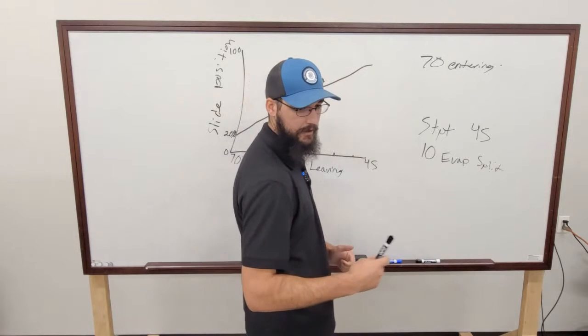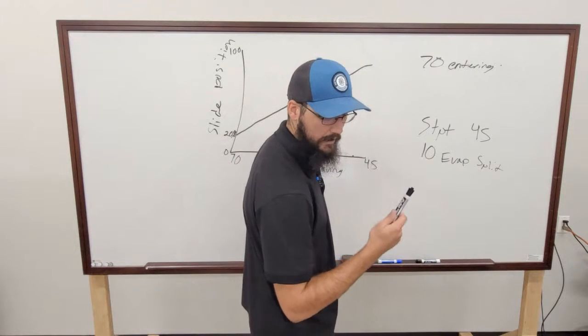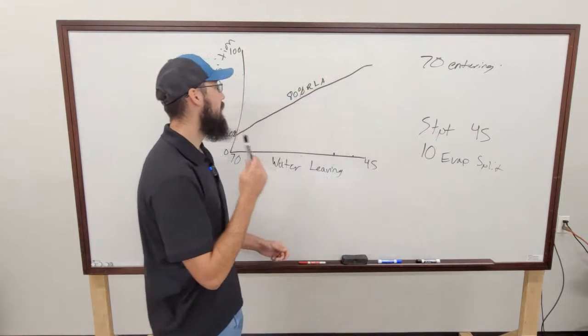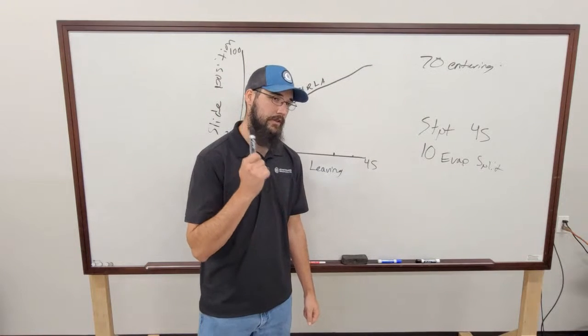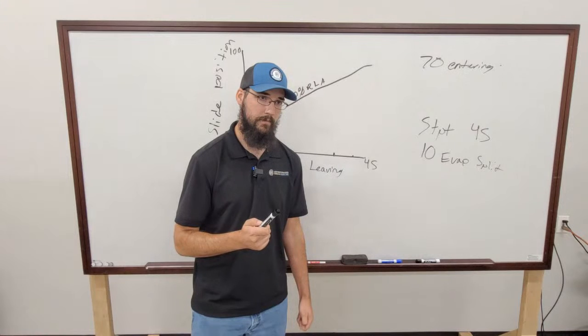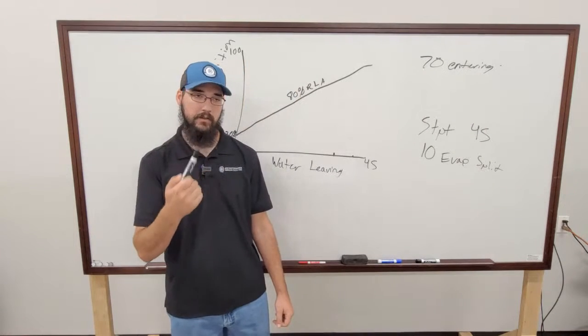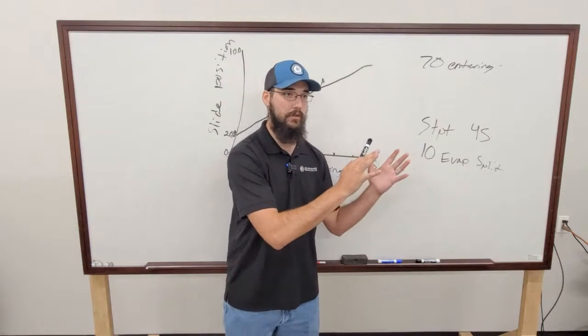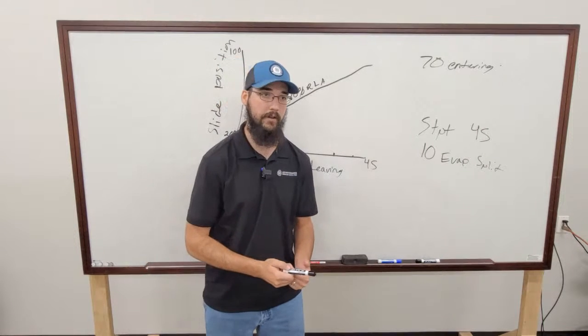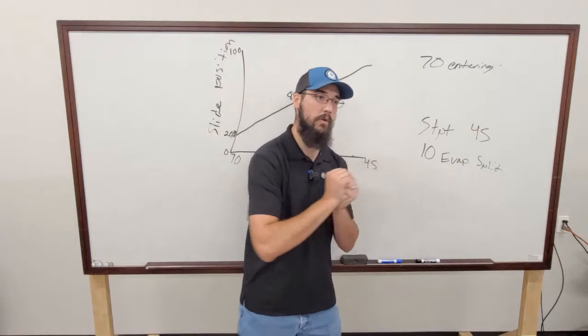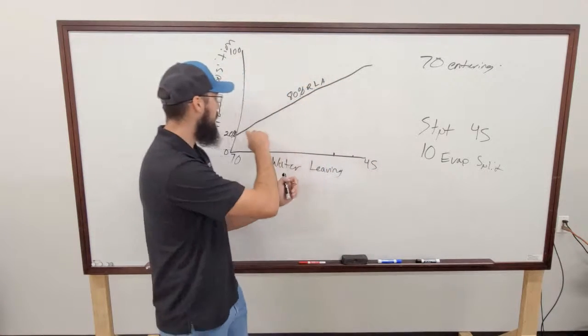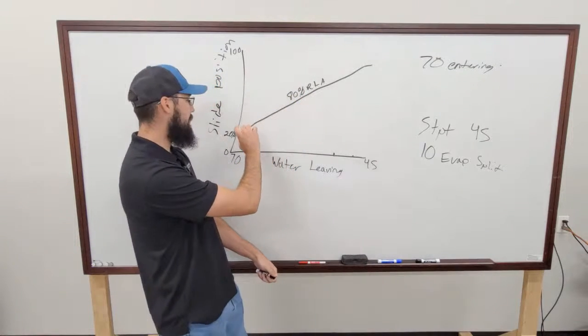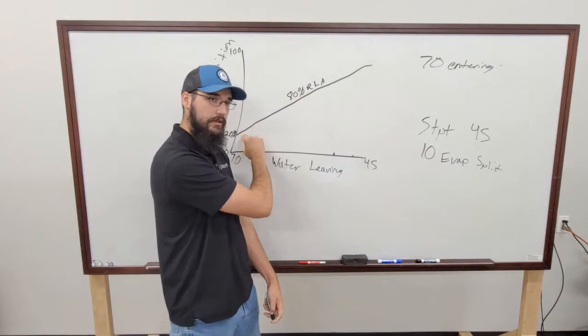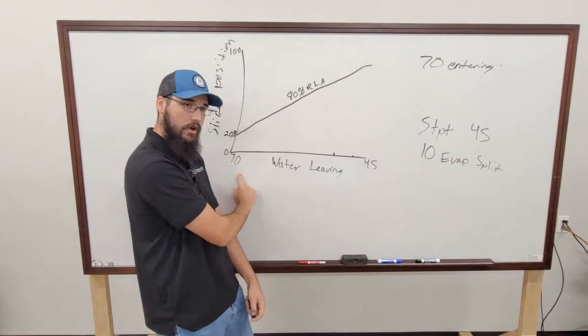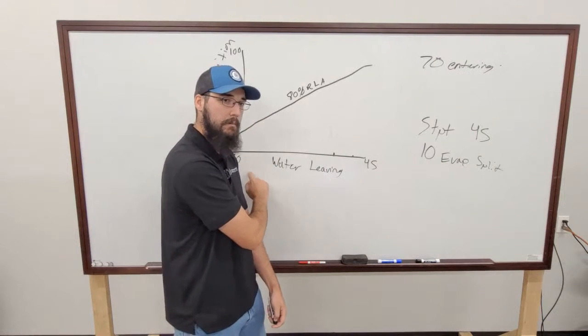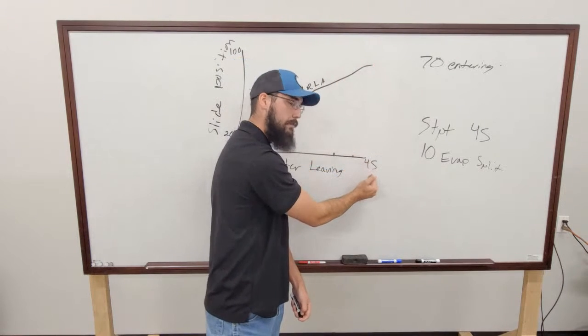So wouldn't head pressure and RLA increase? So keep in mind your head pressure is relative to load. Okay? And I've done several classes in the past talking about subcooling, and head pressure is completely relative to the load that you have on the evaporator. So the more heat we're inputting into the system, the more it has to reject. But ultimately, if we limit that RLA, theoretically, we end up having more head pressure on this end of the spectrum with a really high load on the evaporator, and that head pressure becomes easier to manage as our load on the evaporator reduces.